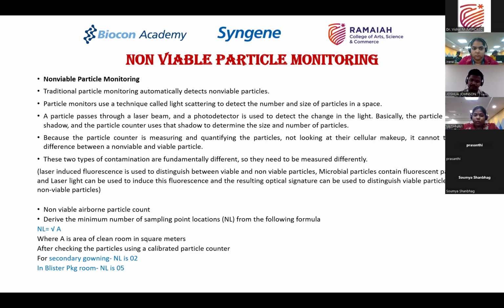There are different instruments placed in different areas. The principle for non-viable particle counting is based on light scattering. A laser beam and photodetectors are placed in an instrument, and it will detect the change in the light.